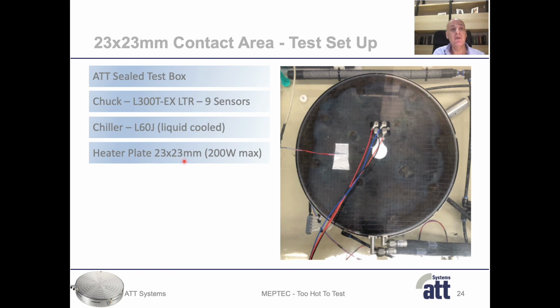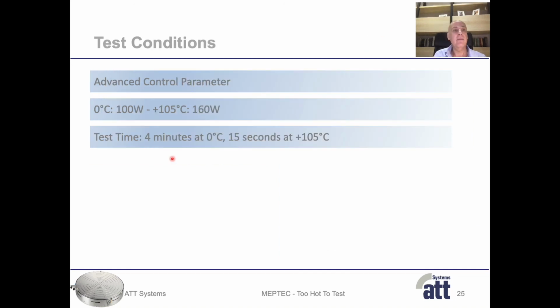This heater was able to provide a maximum power of 200 watt, and actually this was the most powerful one that we could get during that time. This customer asked us to test two different conditions, 0 degrees C with 100 watt and plus 105 degrees C with 160 watt. The test time was 4 minutes at 0 degrees C and 15 seconds at plus 105 degrees C. The goal was to control the temperature increase within 3 degrees C.